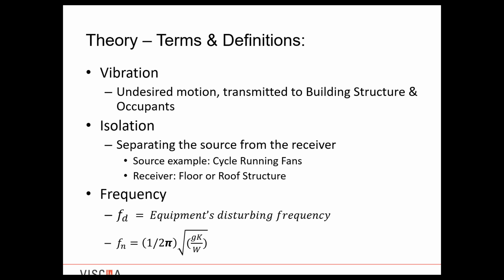Just as a load in a building has a load path, vertical and horizontal, noise through a building has a noise path. And when you're talking about vibration, vibration causes structure-borne noise. So you're basically taking a vibration that's an undesired motion and transmitting it to the building structure. You're causing the building structure to vibrate and to create a noise path. So the isolation, how we counteract this vibration, mitigate it, minimize it, not eliminate it, as John mentioned, is we separate the source from the receiver. The source, an example would be a cyclic running fans, and the receiver would be the floor structure or the roof structure. So we want to separate those with isolation.